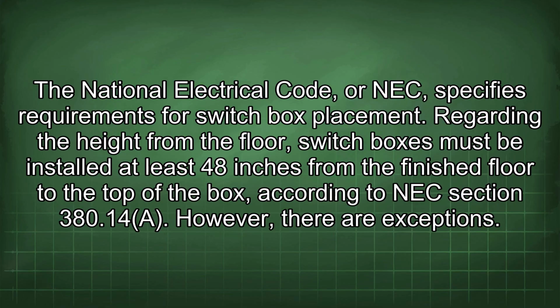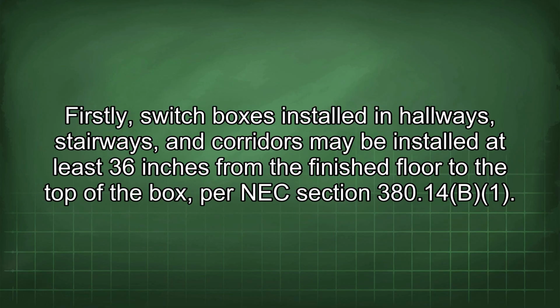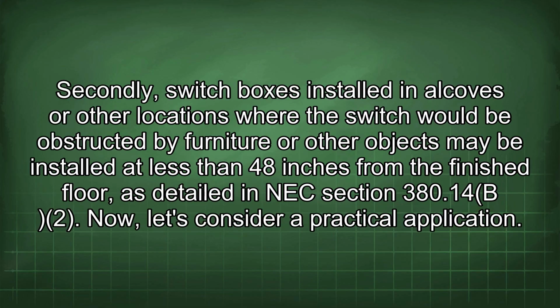However, there are exceptions. Firstly, switchboxes installed in hallways, stairways, and corridors may be installed at least 36 inches from the finished floor to the top of the box, per NEC section 380.14(B)(1). Secondly, switchboxes installed in alcoves or other locations where the switch would be obstructed by furniture or other objects may be installed at less than 48 inches from the finished floor, as detailed in NEC section 380.14(B)(2).